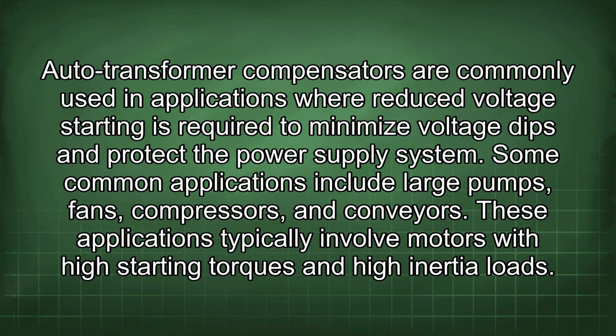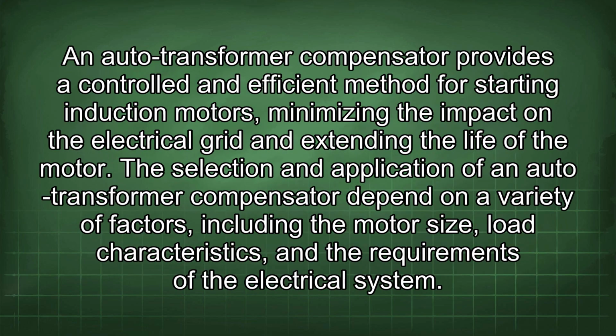Auto transformer compensators are commonly used in applications where reduced voltage starting is required to minimize voltage dips and protect the power supply system. Some common applications include large pumps, fans, compressors, and conveyors. These applications typically involve motors with high starting torques and high inertia loads. An auto transformer compensator provides a controlled and efficient method for starting induction motors, minimizing the impact on the electrical grid and extending the life of the motor.